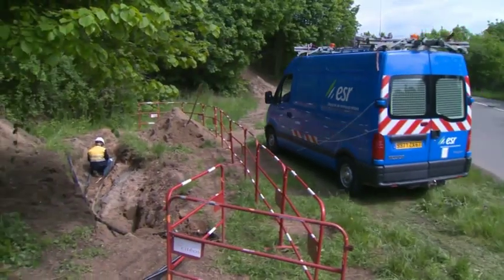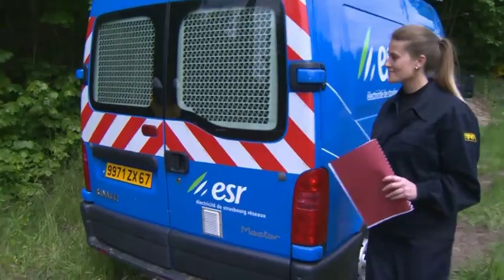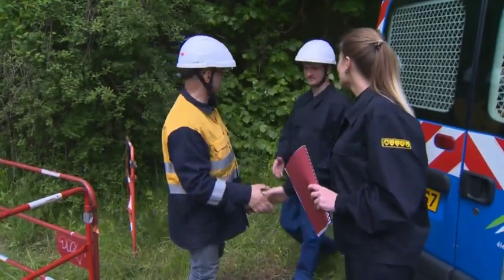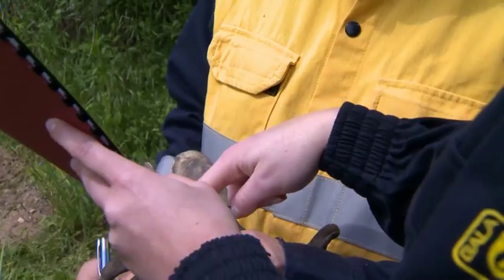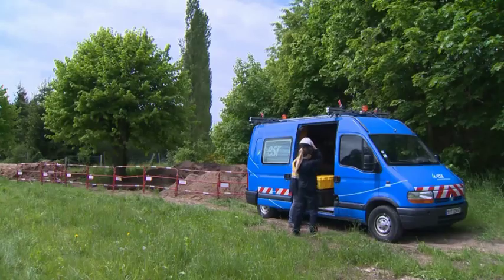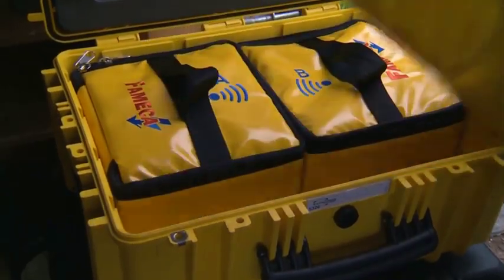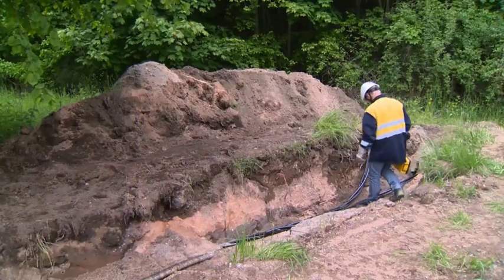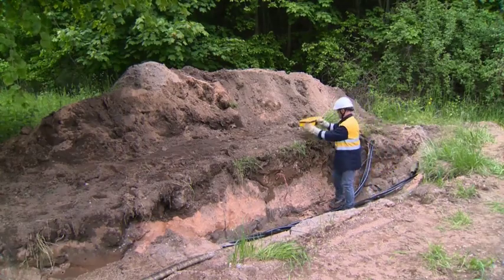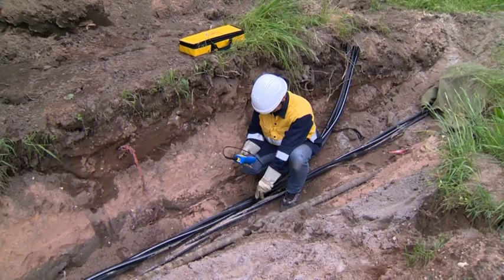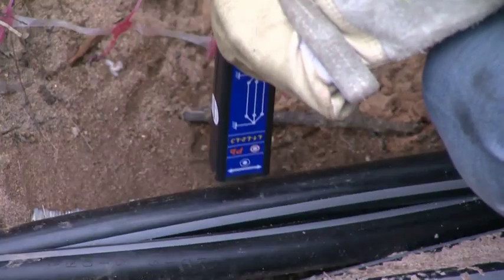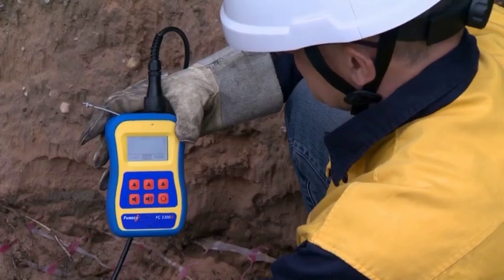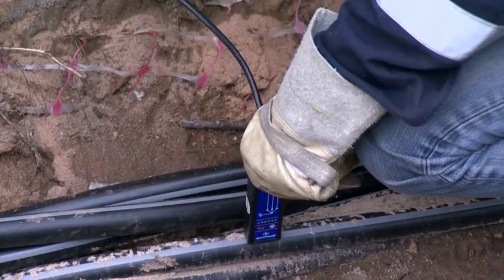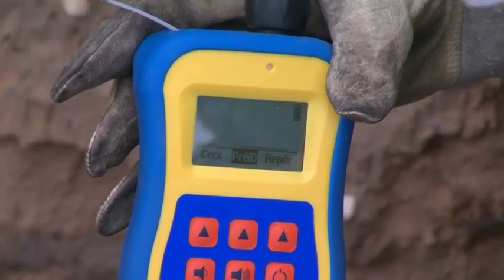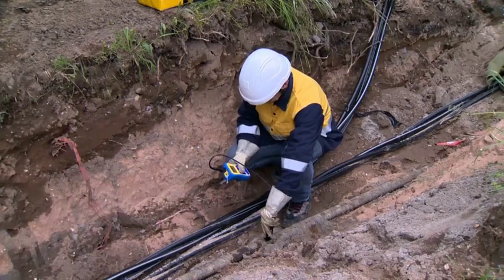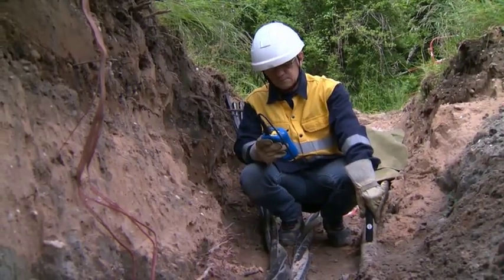Any electrician working on a network is aware that when underground, you can find numerous cables, and you can't make any mistakes. For this, it is crucial to check them all. Cutting the wrong wire means service interruption. This applies to electrical power provided to customers as well as to telephone or cable network services. The blue probe is designed to pinpoint the cable to be identified among others, whatever its type of insulation, screening or length.